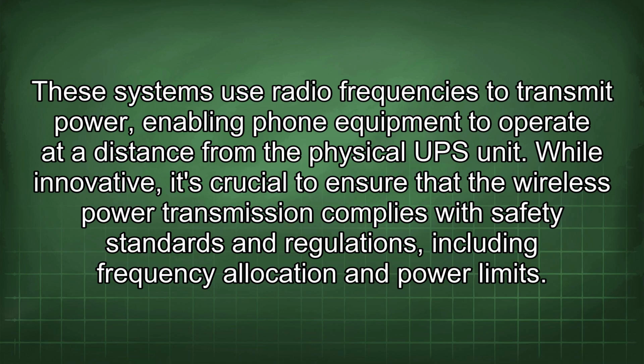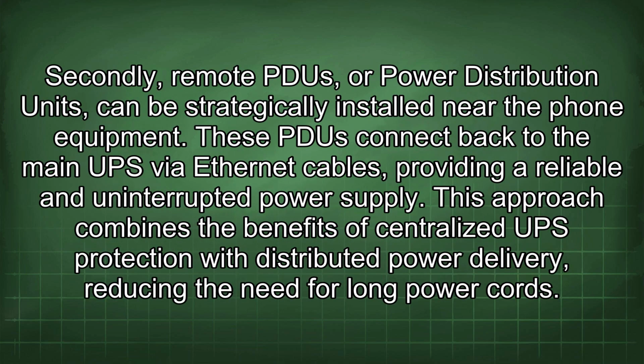Secondly, remote PDUs, or power distribution units, can be strategically installed near the phone equipment. These PDUs connect back to the main UPS via Ethernet cables, providing a reliable and uninterrupted power supply. This approach combines the benefits of centralized UPS protection with distributed power delivery, reducing the need for long power cords.